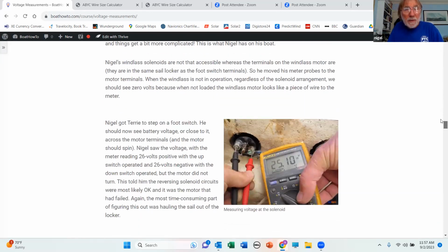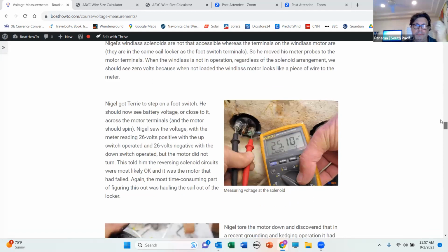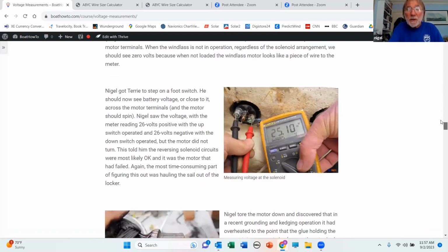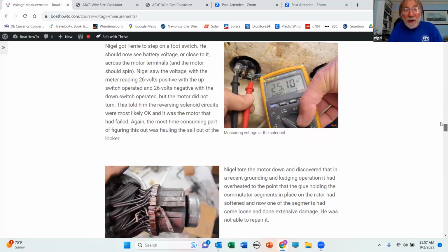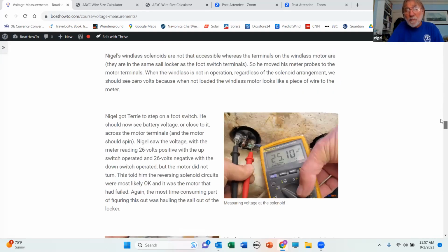So here I am, underneath there, across the switch. Switch is open. I got 25.1 volts. Mine's a 24-volt boat. And when the windlass has failed again, and when Terry steps on the switch, it goes to 0 volts. So now I know the switch is working. Same thing with the up and down, both switches. I get the same result. So I know both switches are working. So the problem is not in the control circuit.